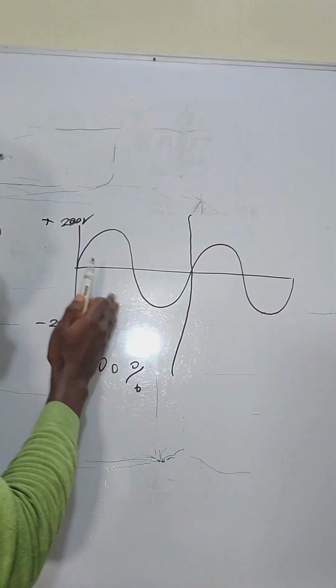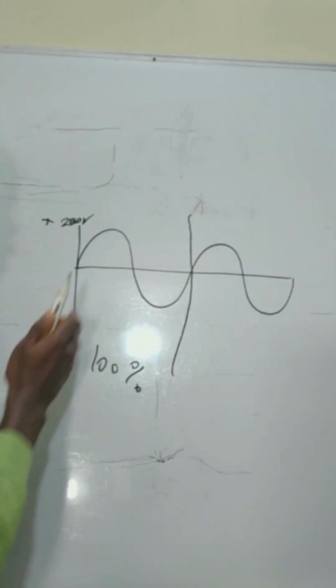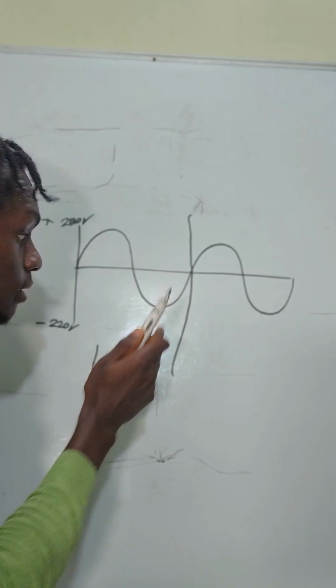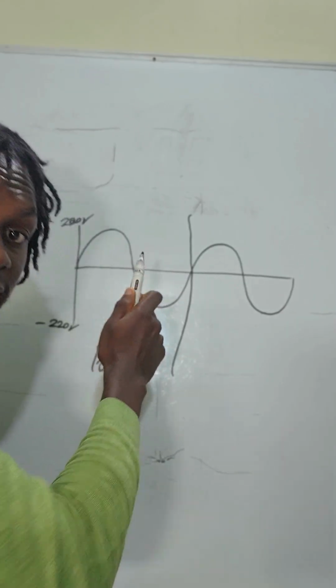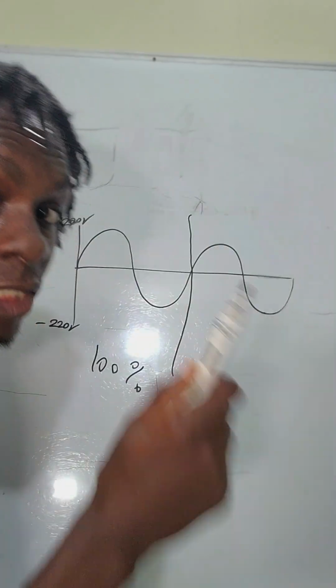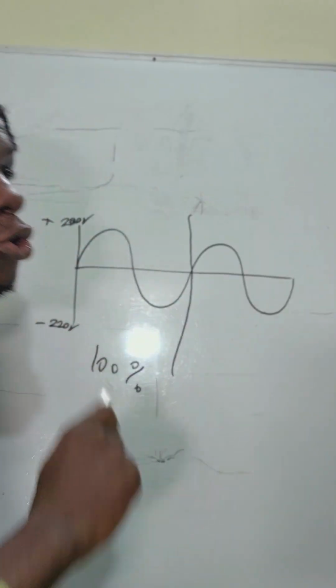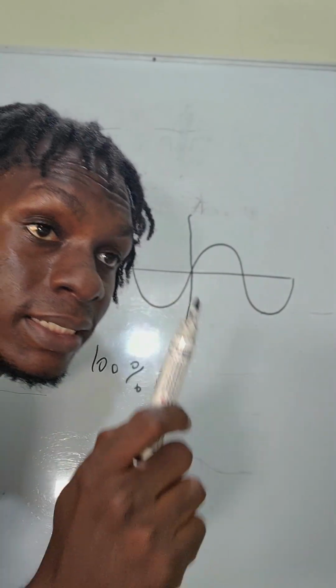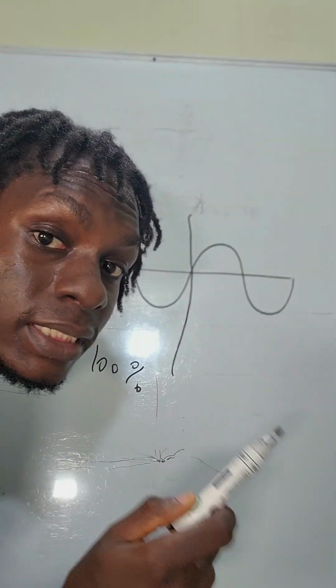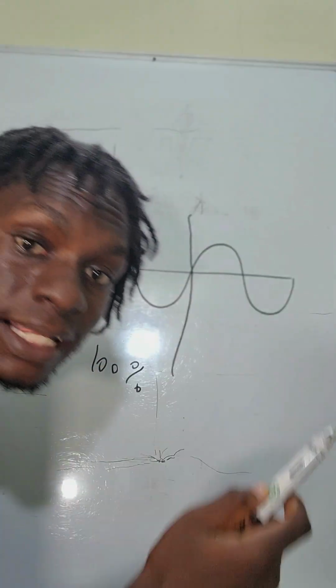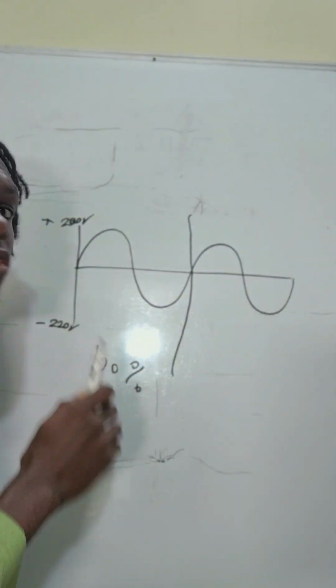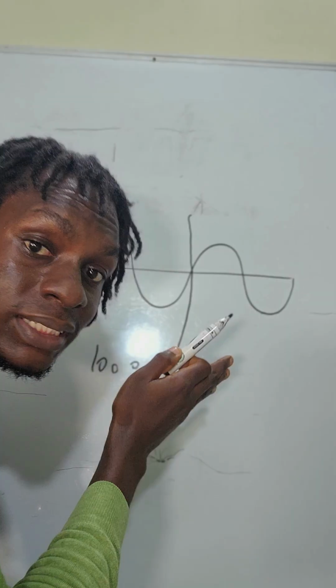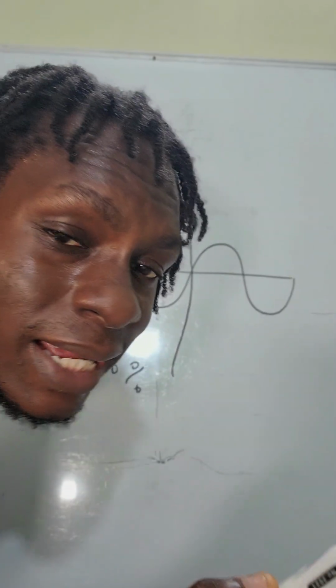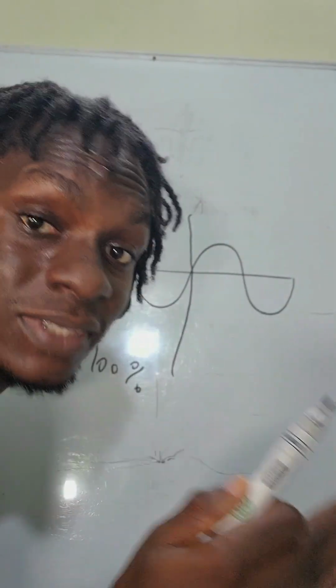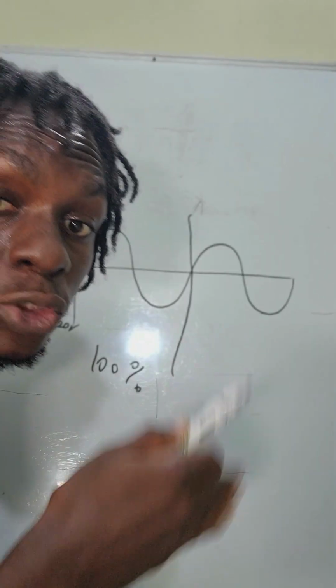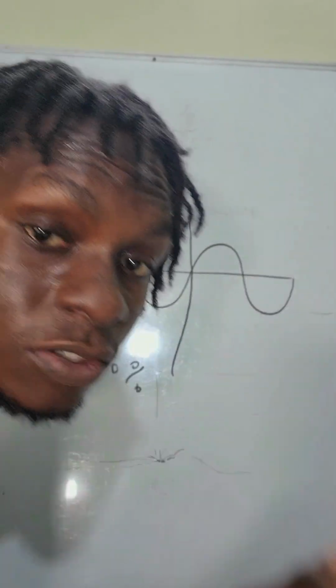None of them is supposed to be bigger than the other. If you are having 40% on the high side and 60% on the low side, it will give your appliances issues. That's where the duty cycle comes in. So some inverters, if they are not properly designed, or even some generators that are faulty, their duty cycle would scatter and give a higher percentage either on the high side or the low side, and that would start affecting your appliance. Sensitive inverters themselves won't even accept that kind of power to pass through or charge the battery with that kind of power, you understand?